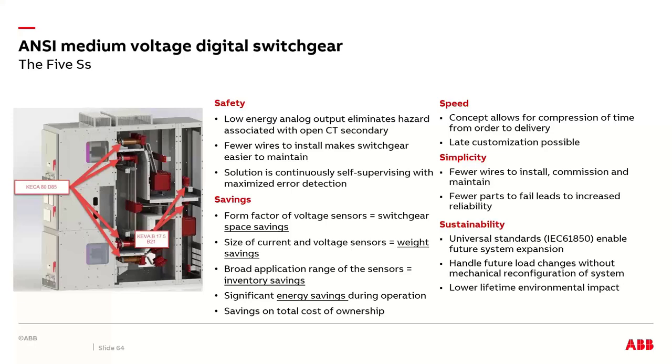Let me go into the benefits of having medium voltage digital switchgear, the five S's, which are most important: safety, saving, speed, simplicity, and sustainability. Of course, safety comes first. We have to determine that this particular application eliminates the hazard of having an open CT secondary. And we have no CT saturation, so that is great. And then the solution is continuously self-supervising with maximized error detection.